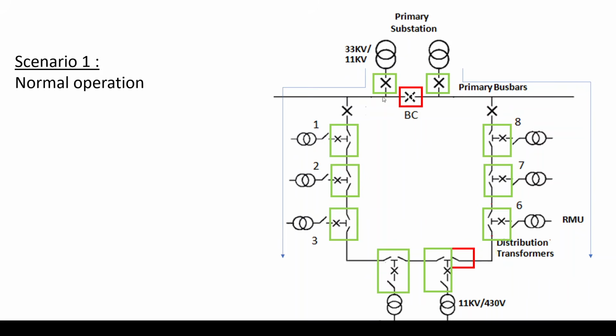So this section is fed by one transformer, this section is fed by another transformer, and my ring is going like that. This is the outgoing from the primary, from here and here. Then the ring is starting, from here to here is a cable. Let's say this is a project several kilometers away from the primary substation. This section is a cable, then going through the first RMU, another connected by cable, maybe this another project number 2 several kilometers away, going by 11 kV cable, RMU, cable, RMU. The same goes on till I reach the closing point of my ring network.